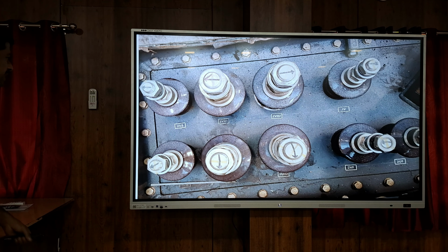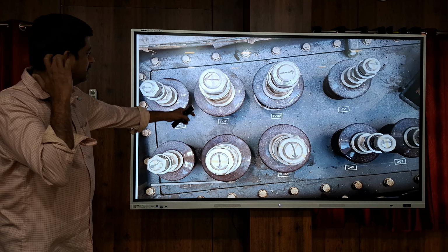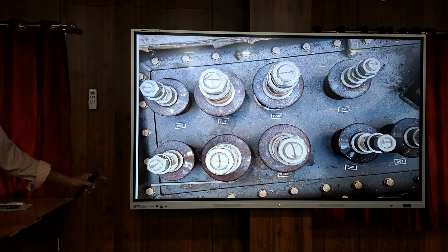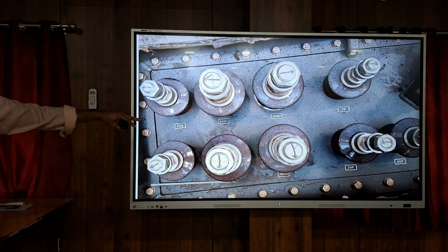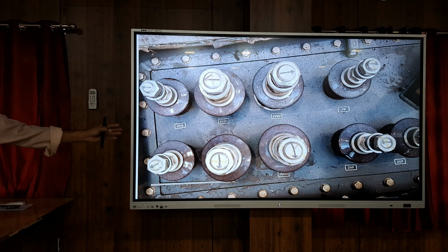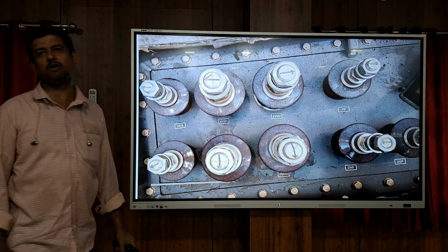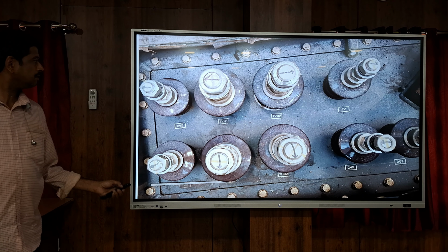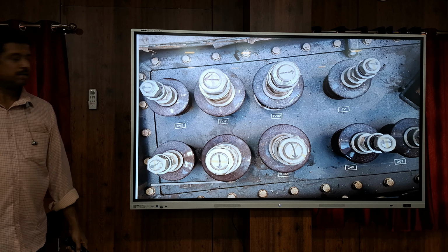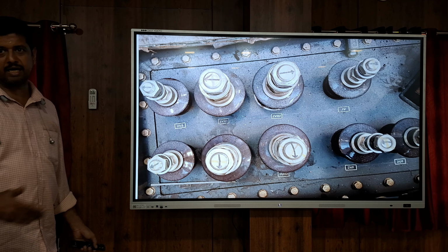This is the transformer bushing. In this, two VH1, two UH1, two UH2 and two VH2 are there for the two hotel loads. VH1 and UH1 are connected to hotel load 1. VH2 and UH2 are connected to hotel load 2 normally. It is connected through 150 square mm 4 kV cables from the transformer bushing to the converter unit. It is directly connected.